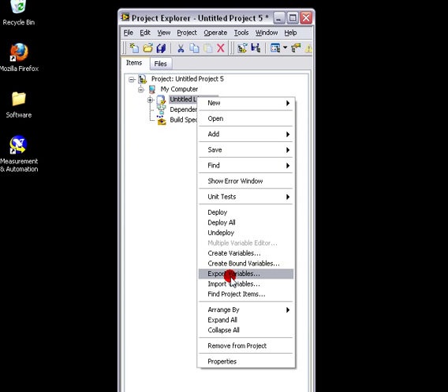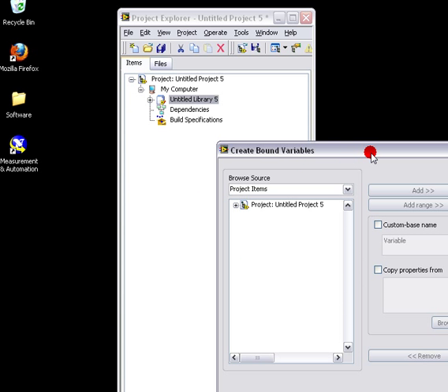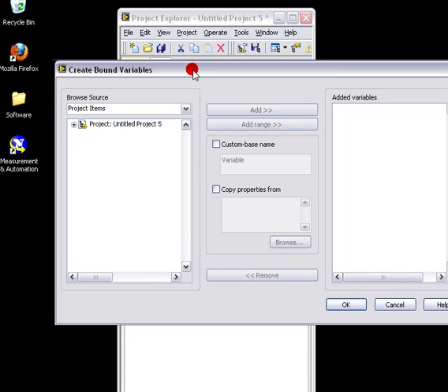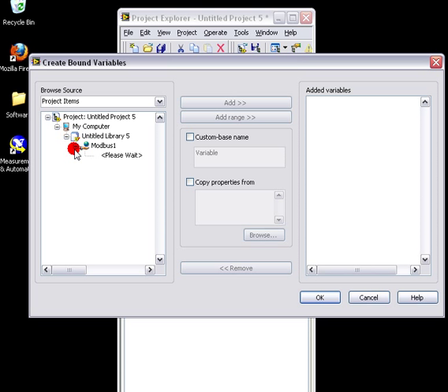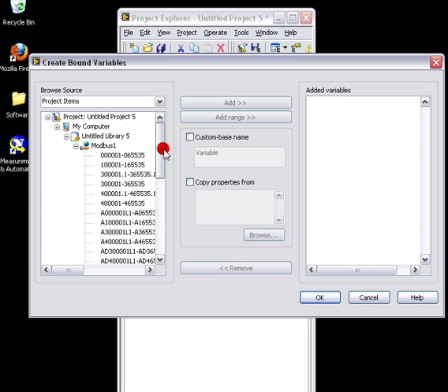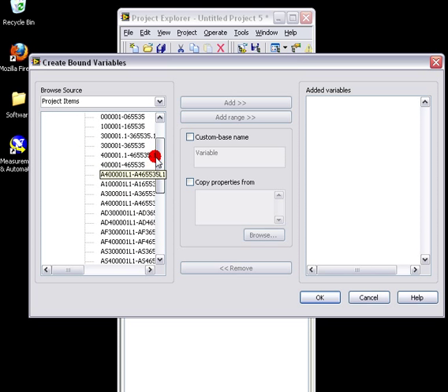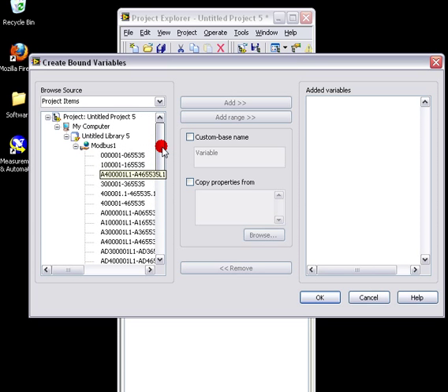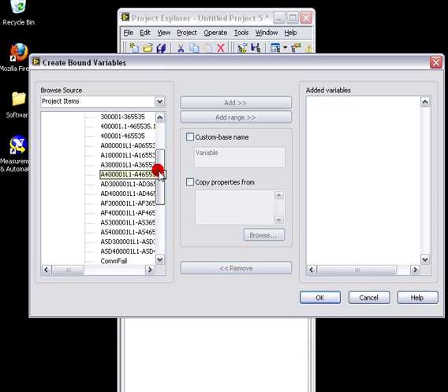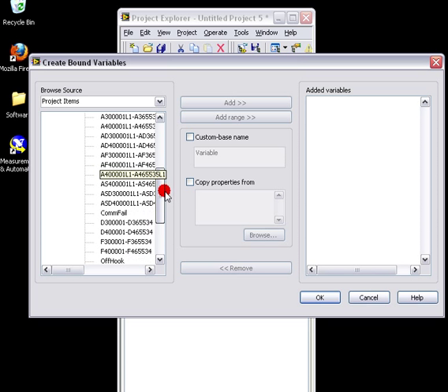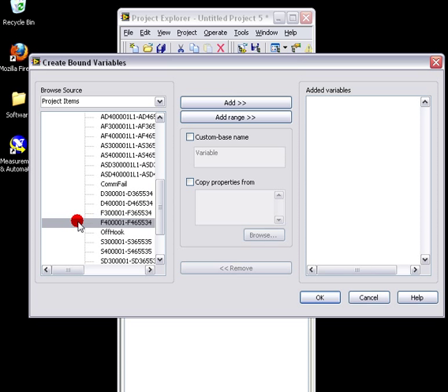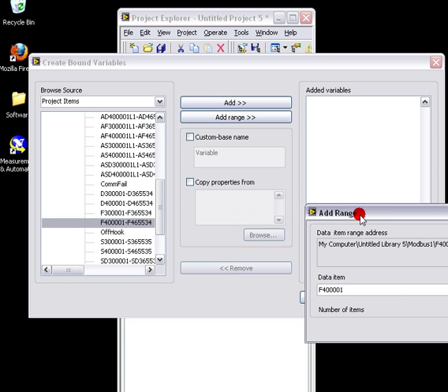Then we'll bind some variables to our newly created IO library. We'll expand the tree, find our different register references here. And with LabVIEW, we need to use the registers with the F prefix for floating point.